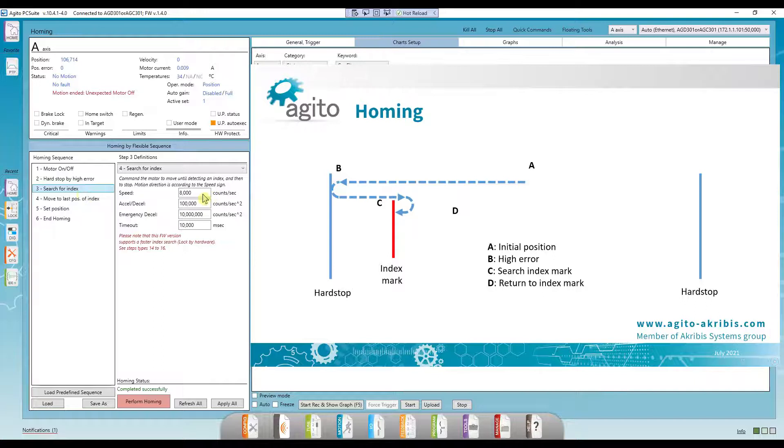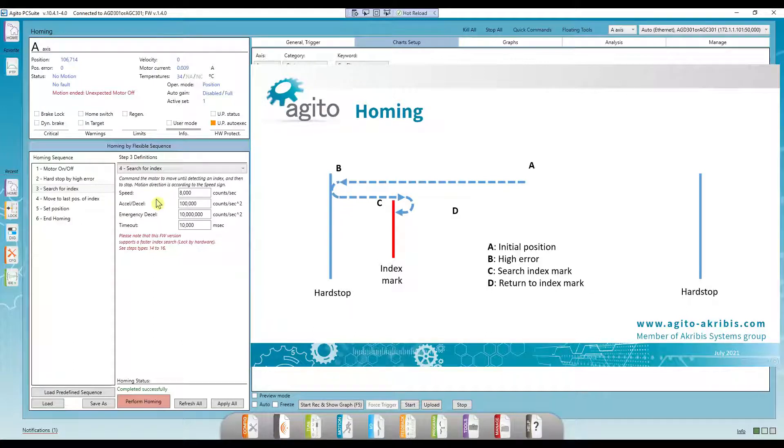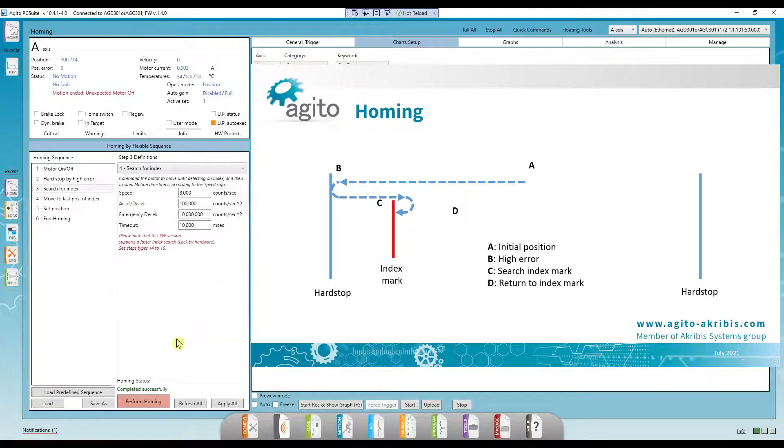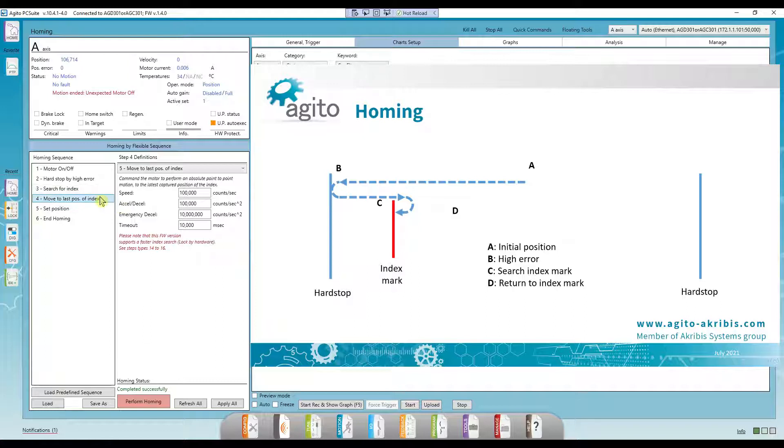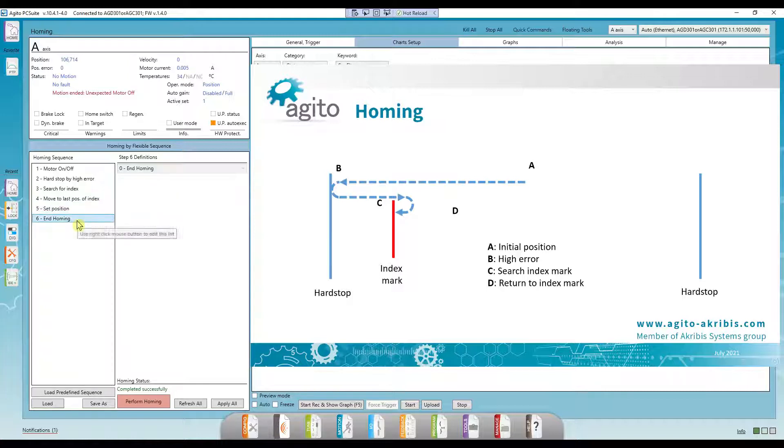Next, we start moving slowly in the positive direction, looking for an index signal. As a side note, we have to make sure we don't move too quickly so we don't miss the index mark. 8,000 counts or less is fine. If we use the position lock we talked about earlier instead, we can move much faster. Okay, once we've reached an index signal, we go back to that index position and set the position there to 0. Then we end the homing process.